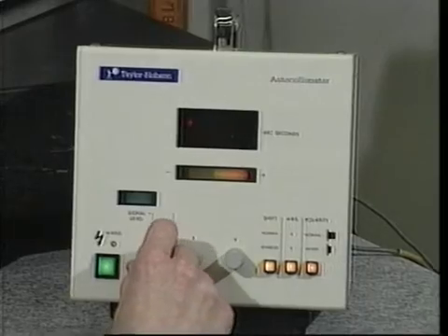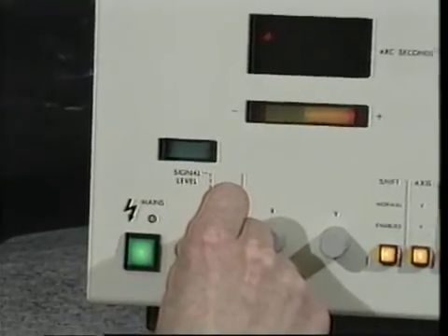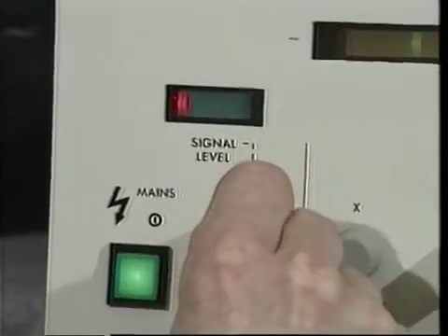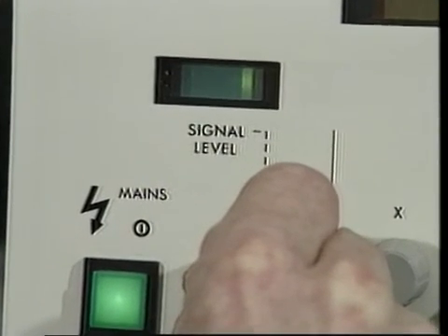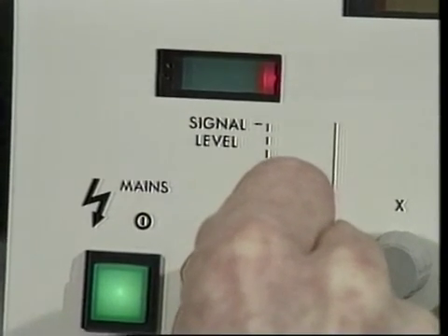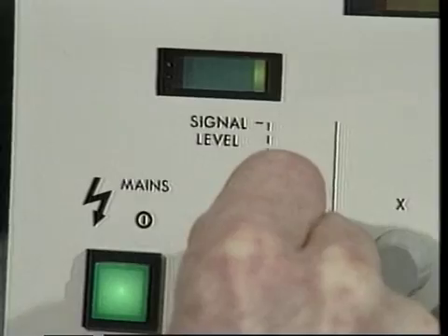Using the signal level knob on the front of the console, tune the signal level to the maximum level possible without causing the received signal meter to enter the red zone.